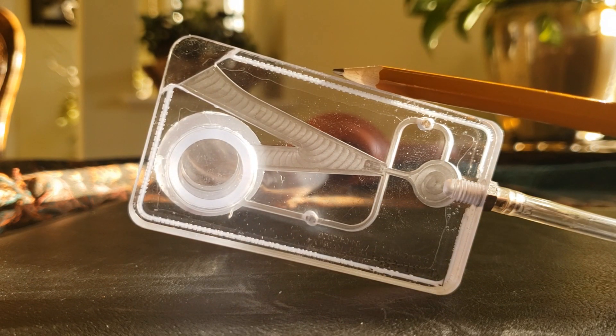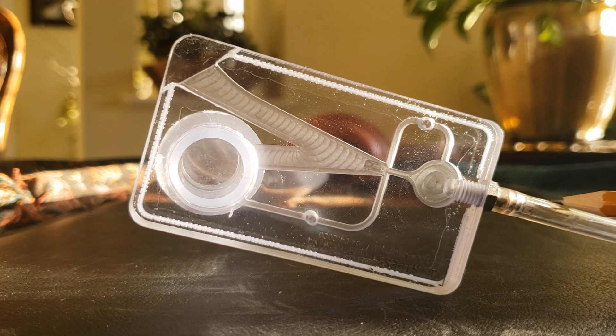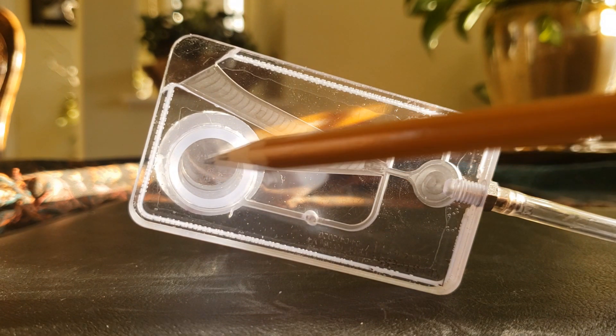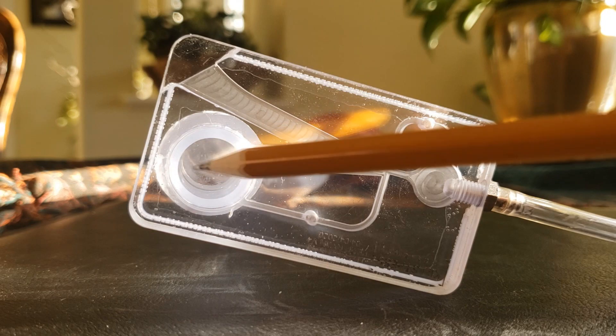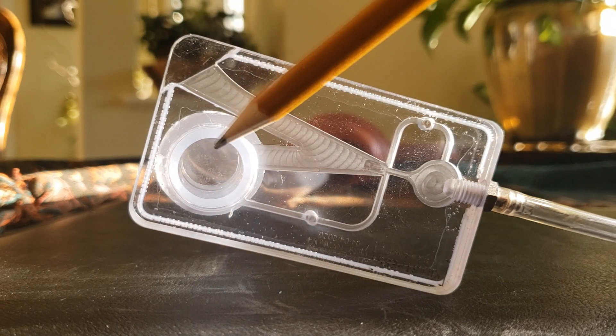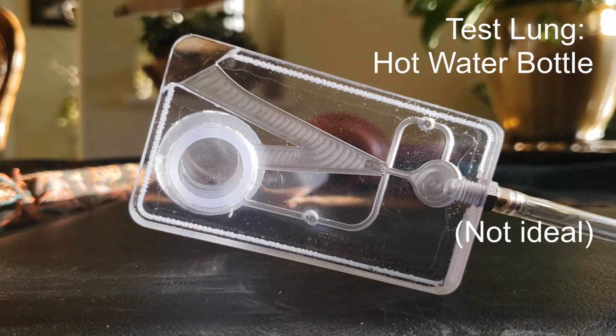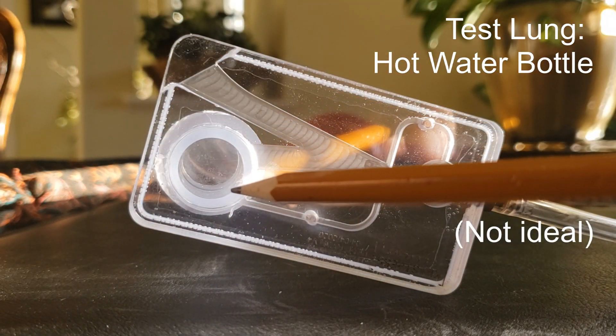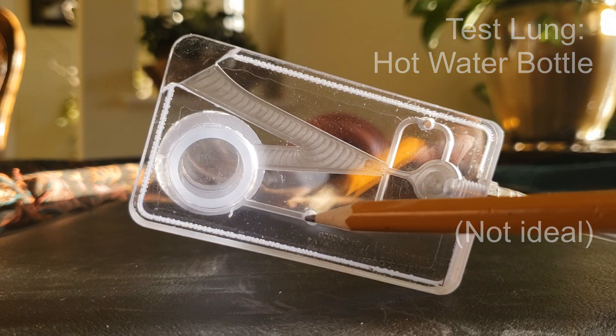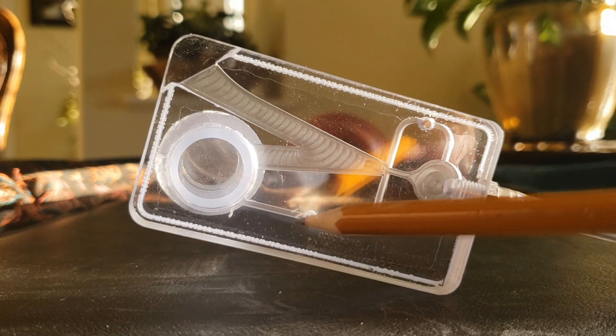Here's how it works. A high flow rate of air comes through here and shoots out through one channel into the lungs. As the pressure builds up in the lungs, that propagates back through here and creates a flow that goes through this channel.